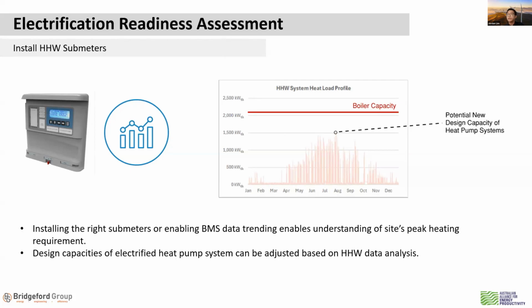It's common knowledge that gas-fired boiler systems are oversized because they are a lot more affordable. However, for heat pumps, given that they're a lot more expensive to implement, you may not want to electrify with a similar capacity to a boiler system, but rather install only what's necessary. But you need data to help you understand what your actual requirement is. Otherwise, there isn't much you can do to justify why or how your building can work just fine with a smaller heating system.